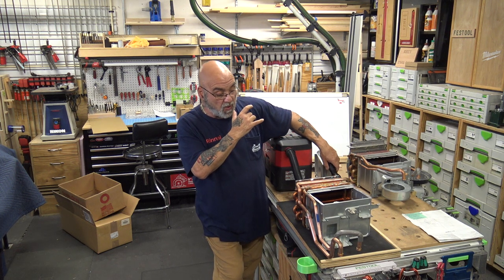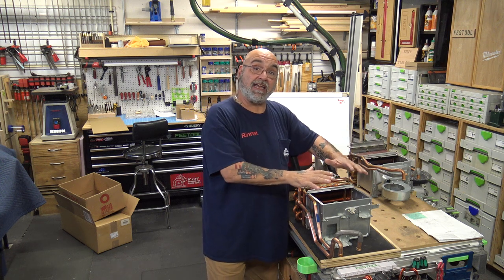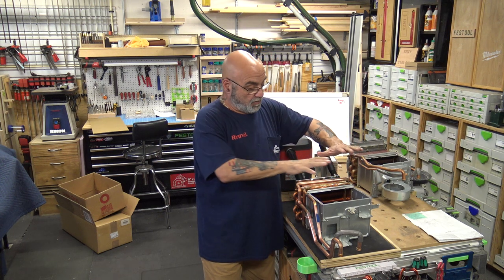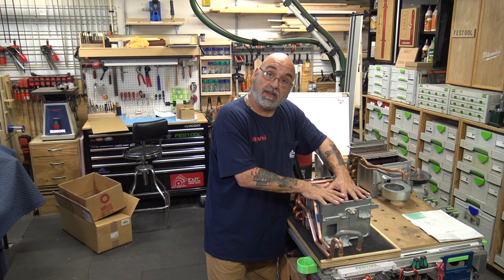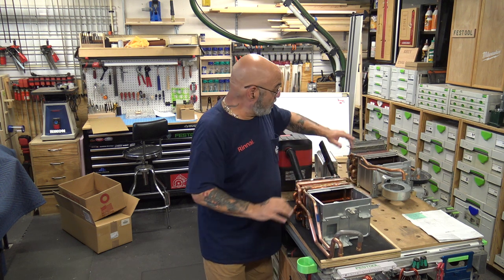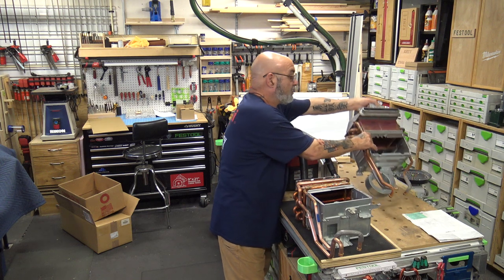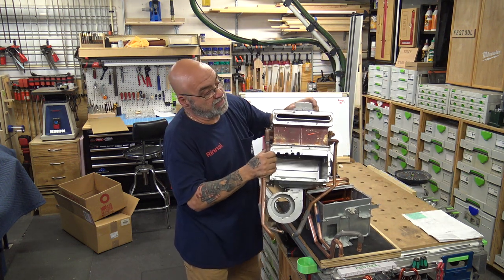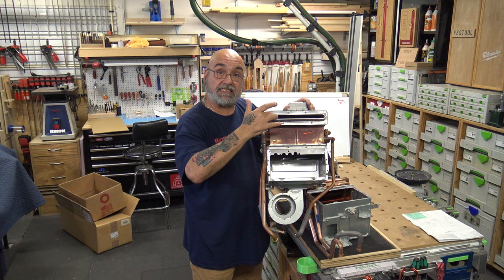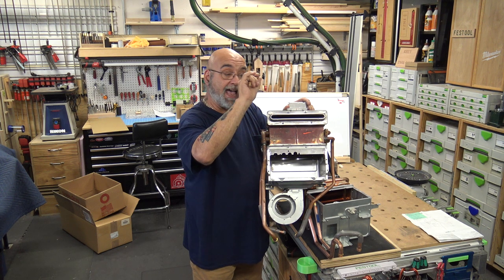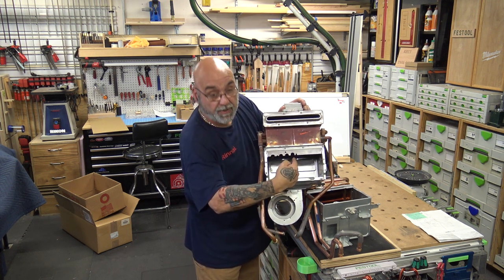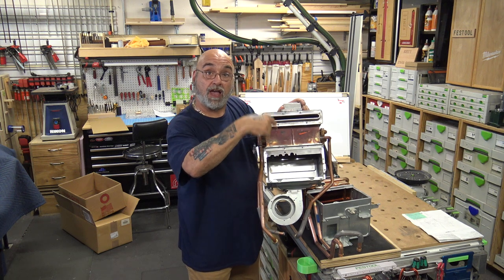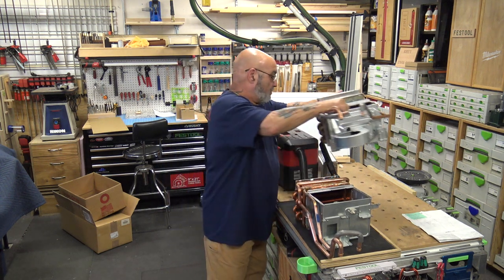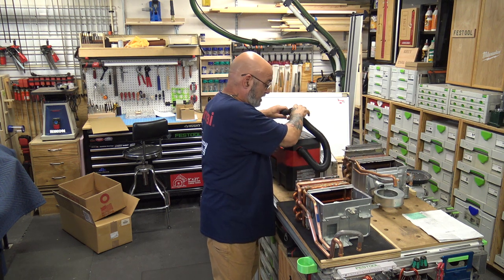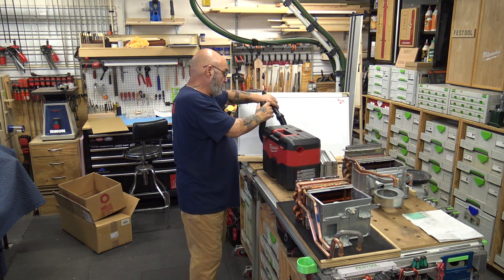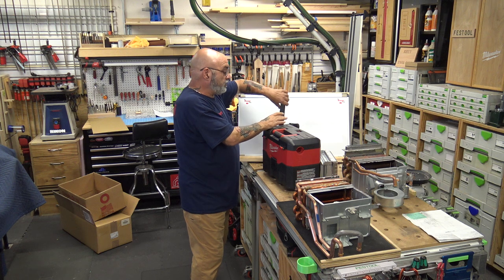What we do in that case is we actually take a plastic garbage bag and put it over this when we blow out. Or on an exterior unit, we tape a plastic garbage bag over this and blow air up into here, or reverse the vacuum and blow it out. But that's what you're going to need to check on the initial call when you get there.